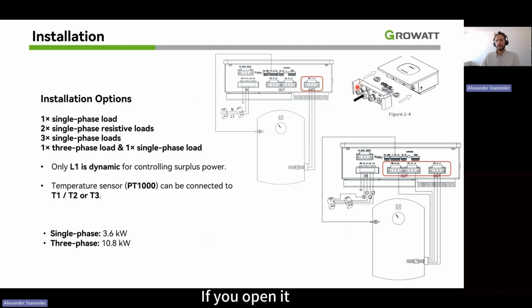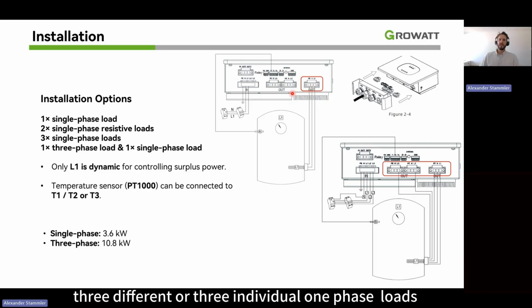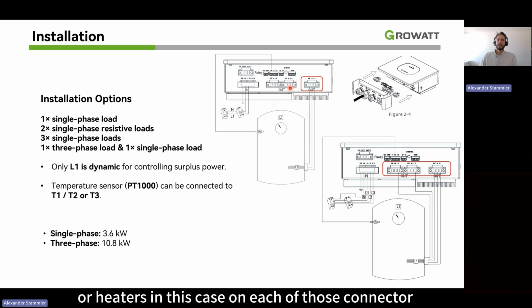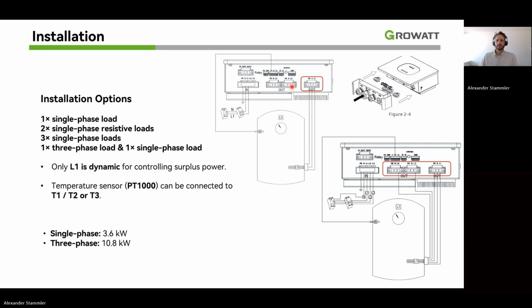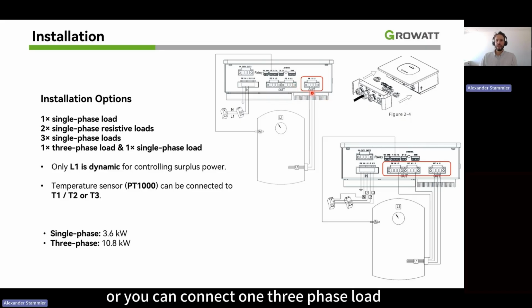If you open it, here are all the connectors. Here you only route through the cables, and then here you see the connectors. In this example, I have a one-phase heating element, which is connected here to L1. So we have here L1, N, and PE. Here we have L2 and L3. So you can connect three individual one-phase loads or heaters, in this case, on each of those connectors. Or you can connect one three-phase load.